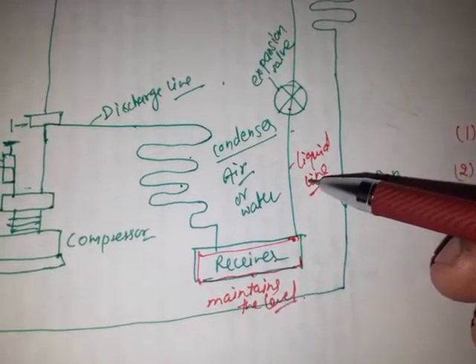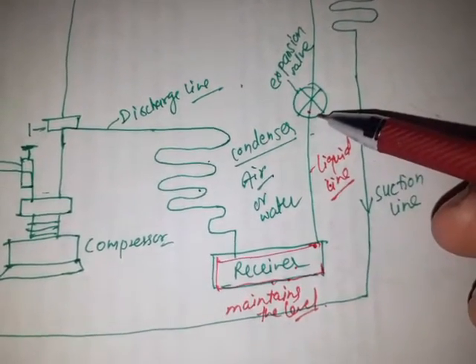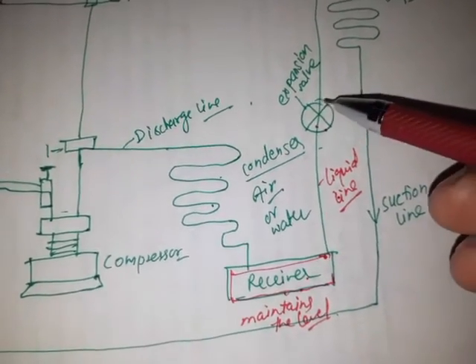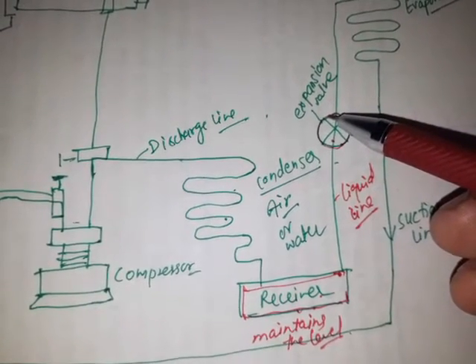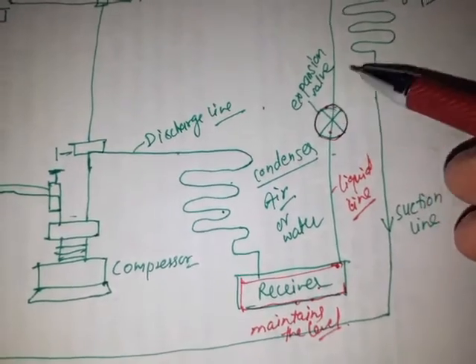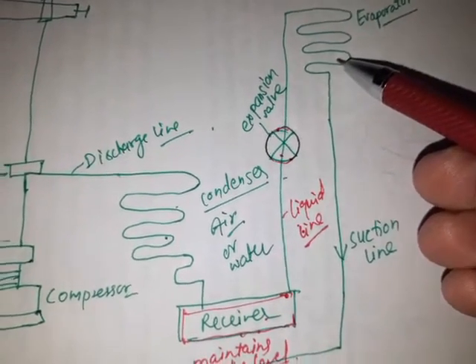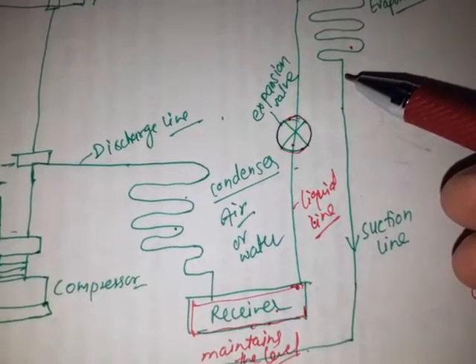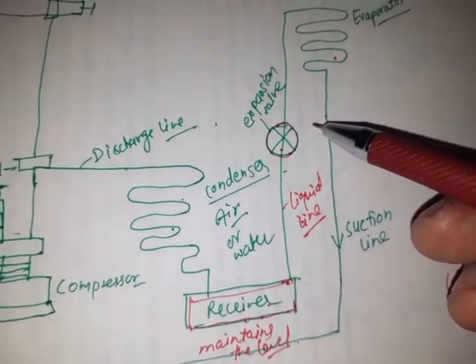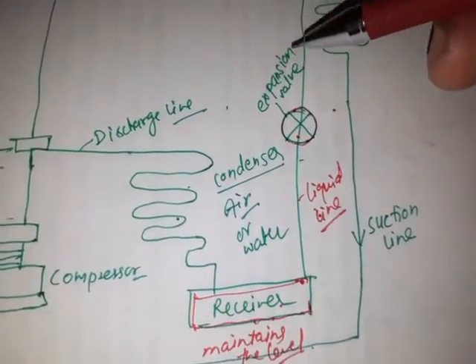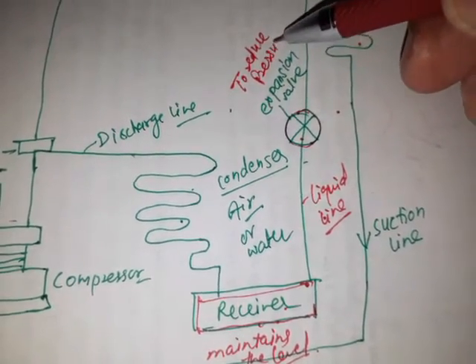The liquid line carries the liquid refrigerant from the receiver tank and conveys it to the expansion valve. The main function of the expansion valve is to supply the proper amount of refrigerant to the evaporator, but after reducing the pressure, so that the refrigerant may take sufficient heat from the refrigerating space during evaporation. The main work of the expansion valve is to reduce the pressure of the refrigerant.